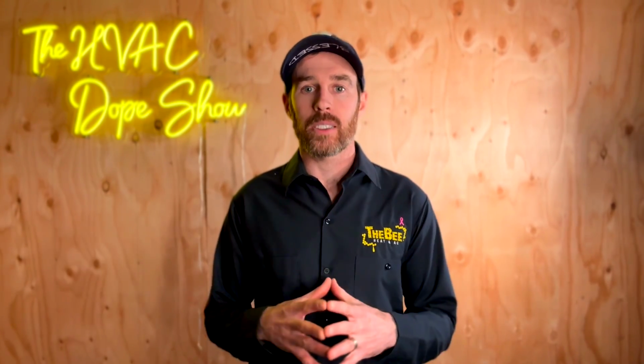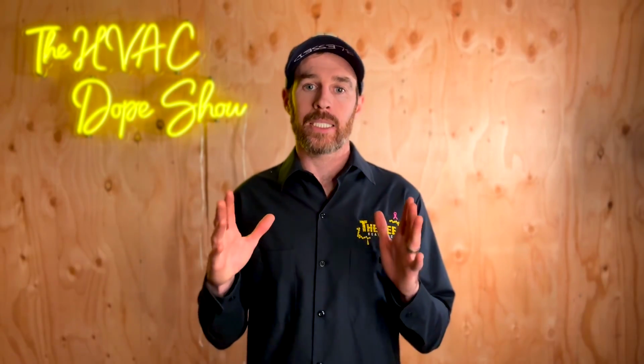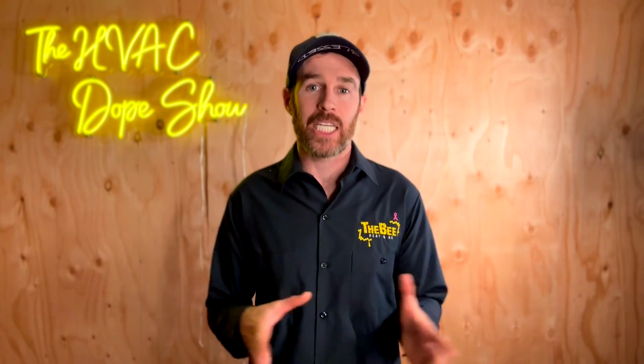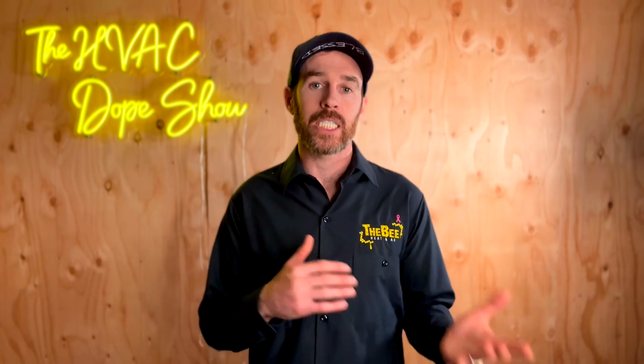So we will talk about some of the things that need to be done as far as installation best practices on a high efficiency system to make sure that it works reliably, as well as some of the maintenance items to make sure that your system works trouble-free on a consistent basis. The two biggest maintenance items that will prevent all issues in HVAC in general, but especially with high efficiency furnaces, is number one, cleaning out the condensate trap. That's specific to high efficiency furnaces. And number two is changing your filter. Changing your air filter is a DIY item that most homeowners can do. However, the condensate trap is something that should be cleaned out by your technician during yearly annual maintenance.